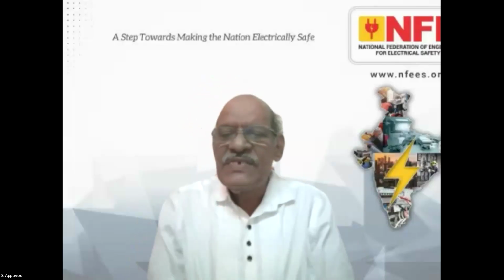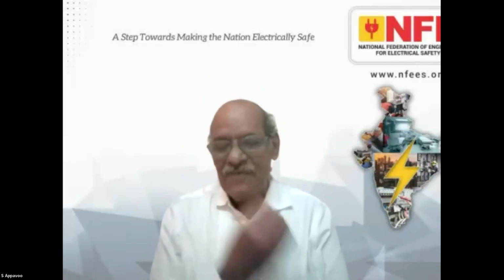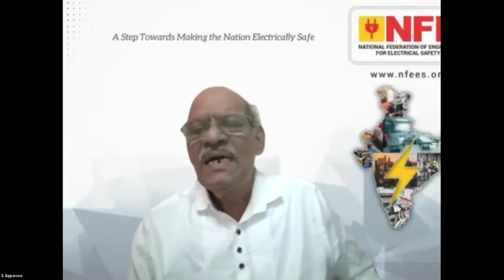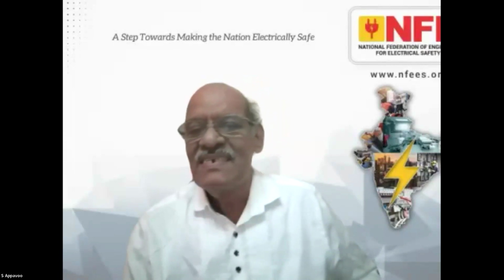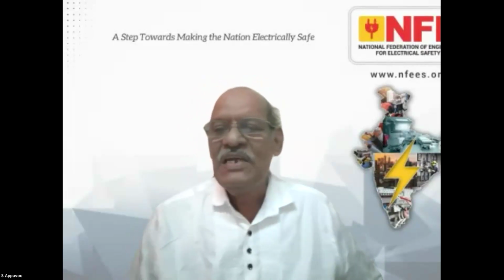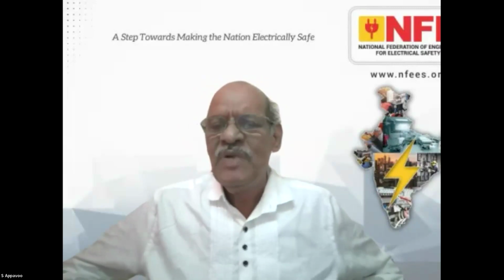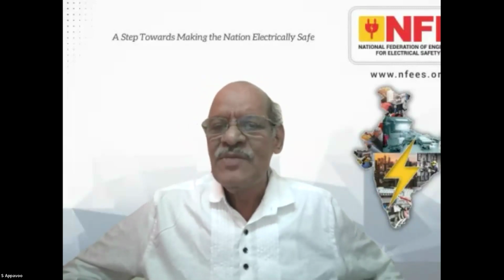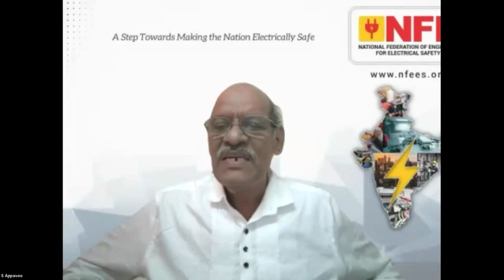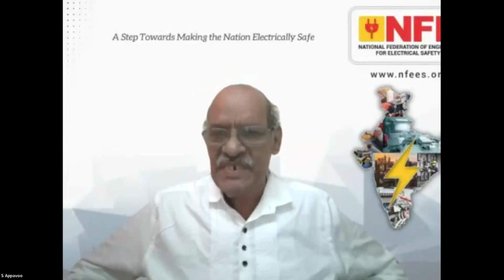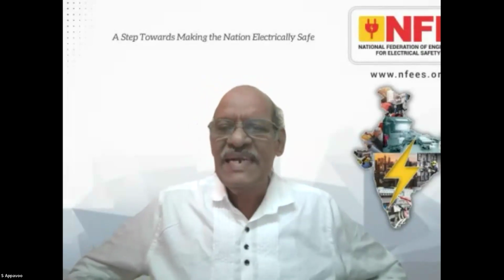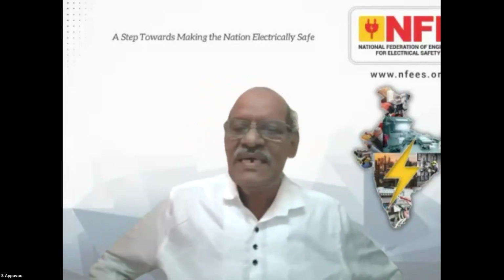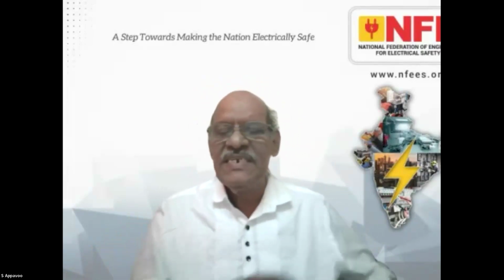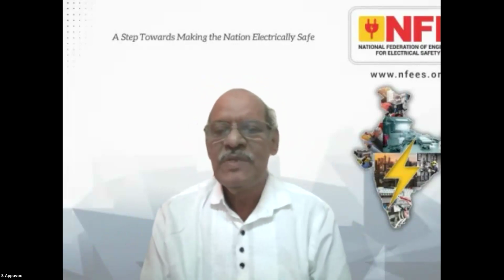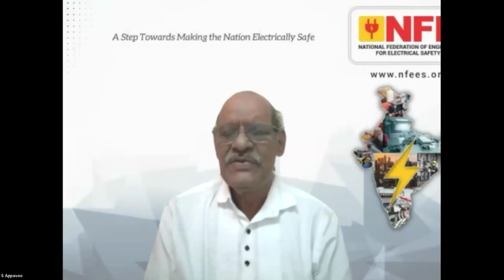Okay. Actually, this is a question raised everywhere: the earth resistance value. However, there is a clause in IEC regarding the value that is applicable for type A. But type B is the recommended arrangement, the most adapted for buildings, where it will serve not only lightning protection but many other safety aspects also. And the potential grading of the building itself will be reduced. The touch potential itself, when a person approaches the building from the substation, will get reduced.